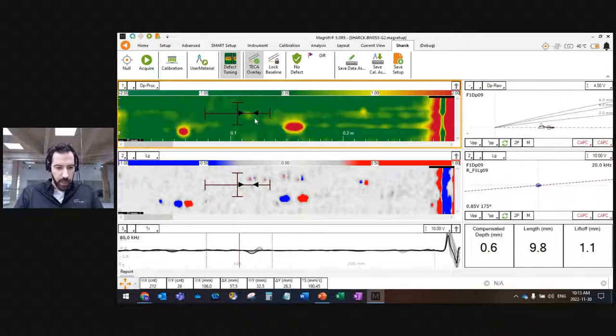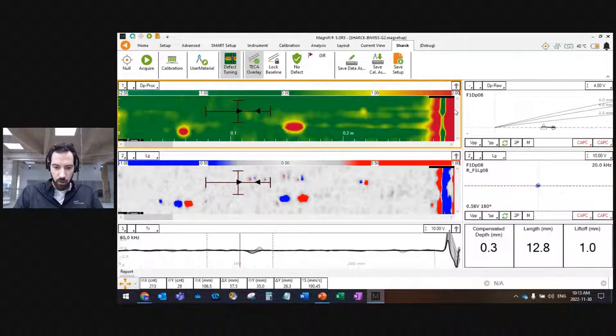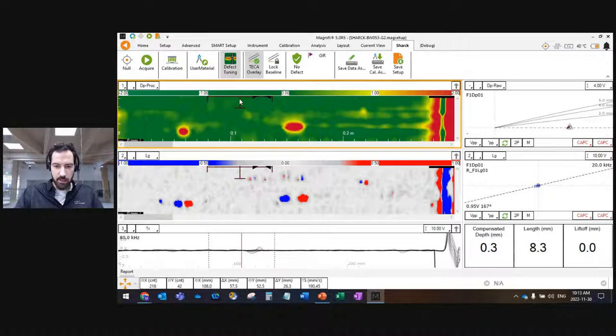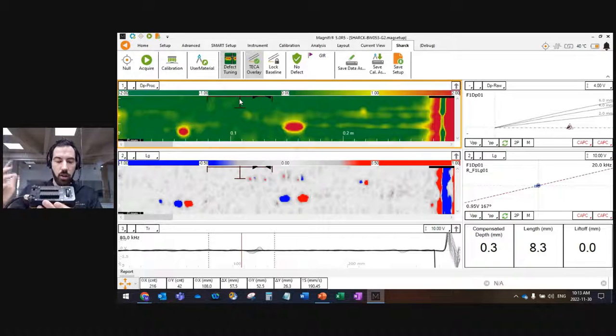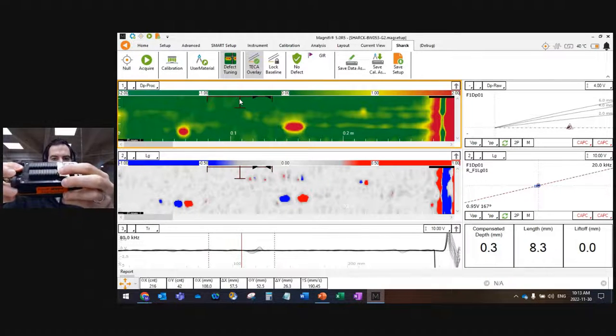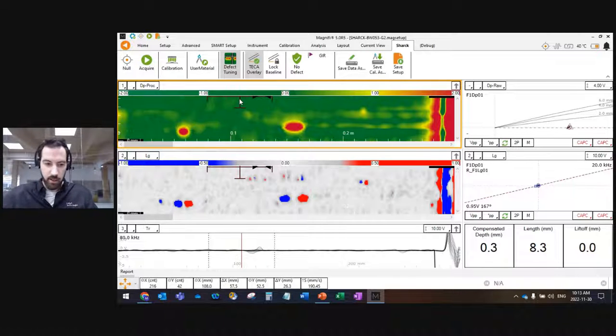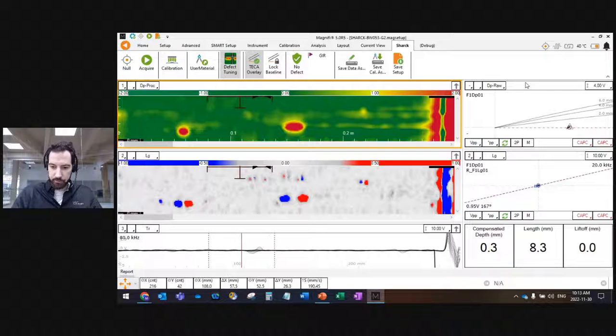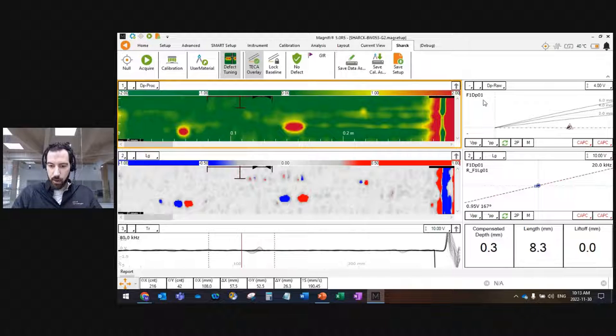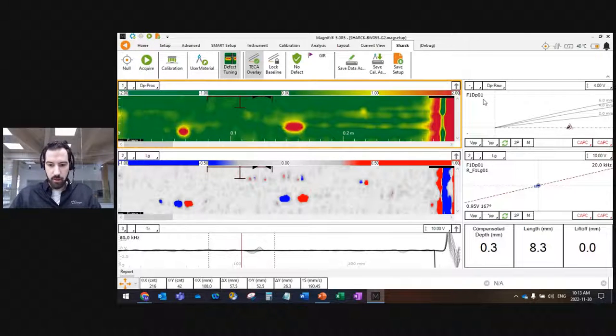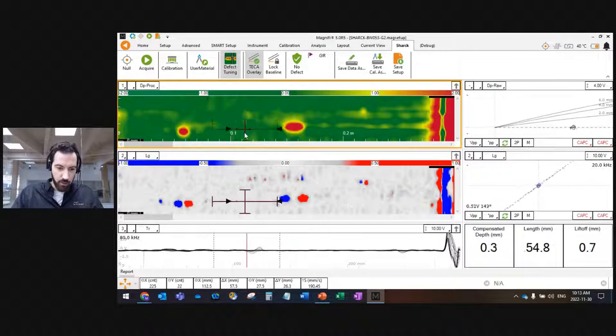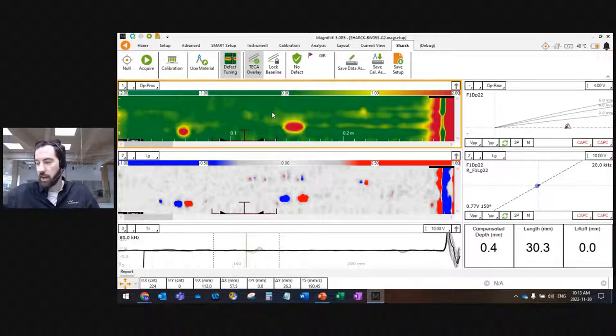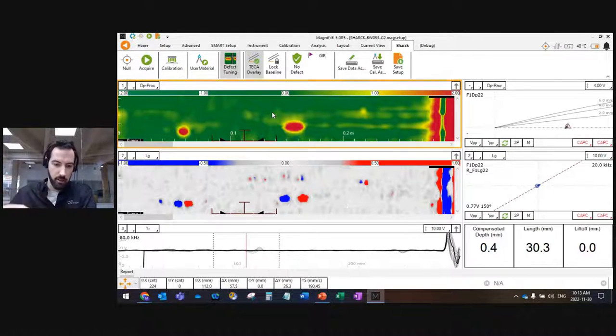It also affected the depth. Because if I have a pipeline alloy and a pressure vessel alloy, in Asia for example, they use some types of alloys that are different from North America that have different properties, different tensile strengths, and different magnetic properties. We need to compensate for it accordingly. This is what the software is doing. What are we looking at exactly? This C-scan here, let's consider that top view where you have the green and red coloring. Every single of those lines is made from the signal of one sensor.